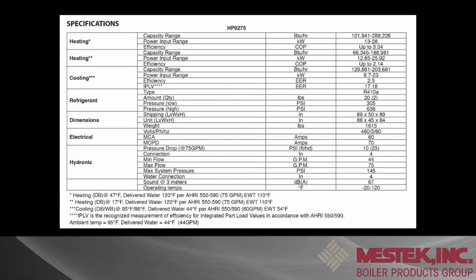On the pressure drop side, at 75 GPM, our head pressure is about 23 feet of head, 10 PSI. So when we're sizing our pumps, we're going to look at that GPM, look at the head pressure, add our piping, and we're going to size our pump accordingly.